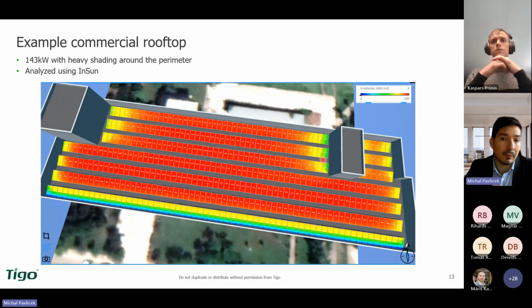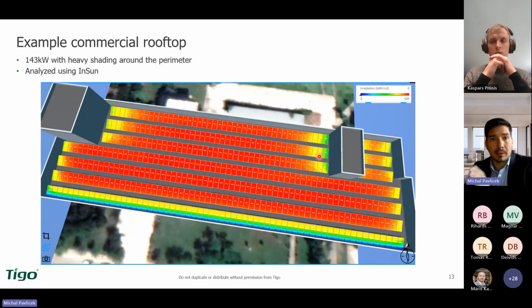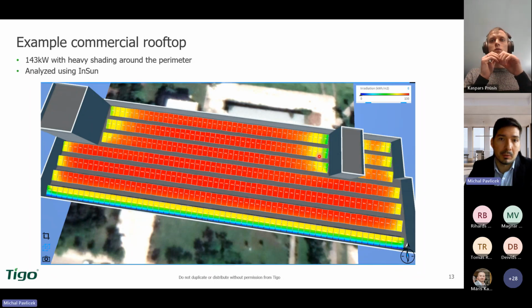Now, the shade is one of the extremes. Of course, if you look at the list of your PV modules on the flash test, typically you see every module has a slightly different current. The optimizer is also able to align those currents on every module. So even though you are in a string of perfect modules on day one, optimizers are able to optimize even those small differences of currents and improve the power generation. So it works anytime at every module, and it's always improving the power generation to avoid the losses.